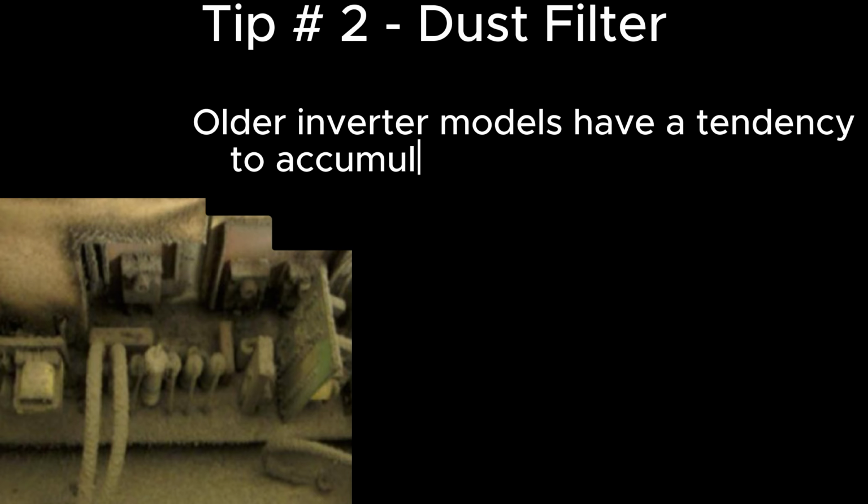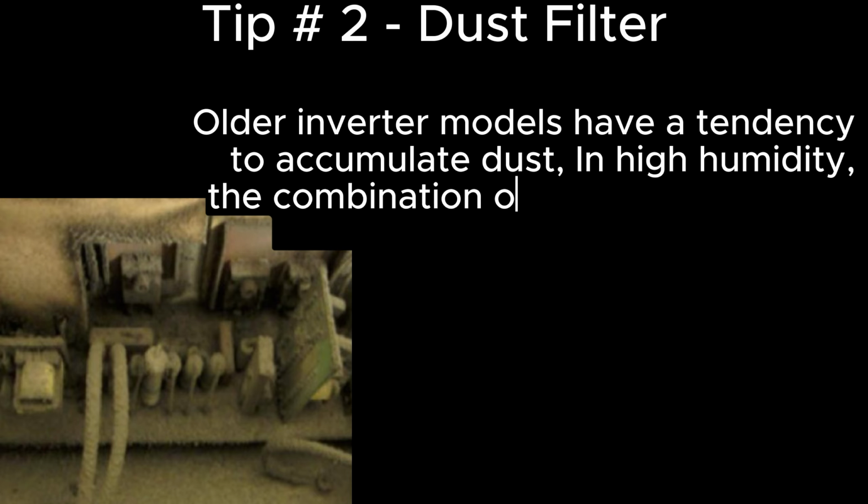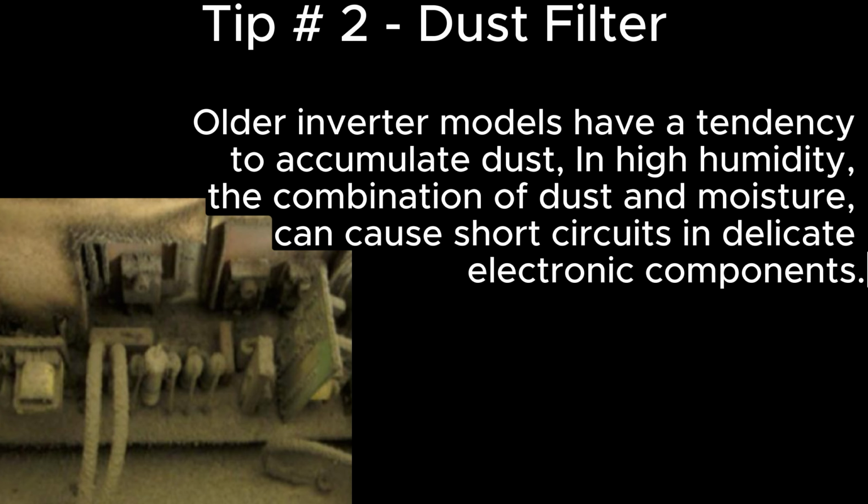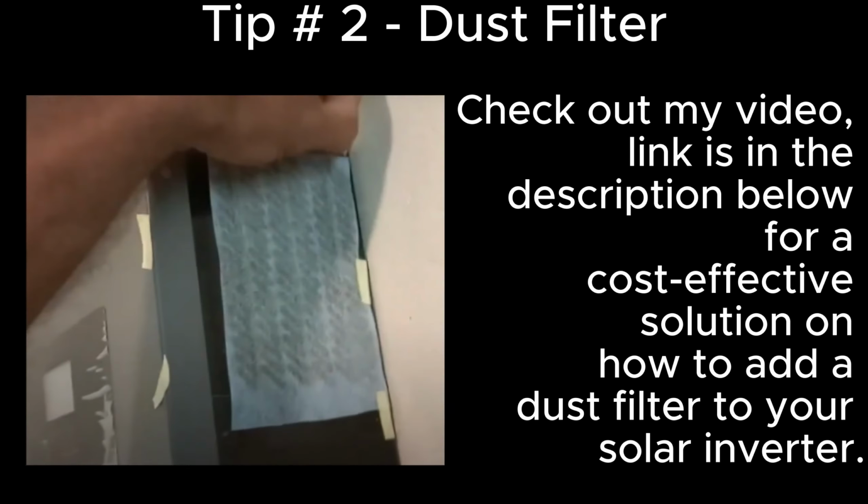Tip number 2. Dust filter. Older inverter models have a tendency to accumulate dust. In high humidity, the combination of dust and moisture can cause short circuits in delicate electronic components. Check out my video, link is in the description below, for a cost-effective solution on how to add a dust filter to your solar inverter.